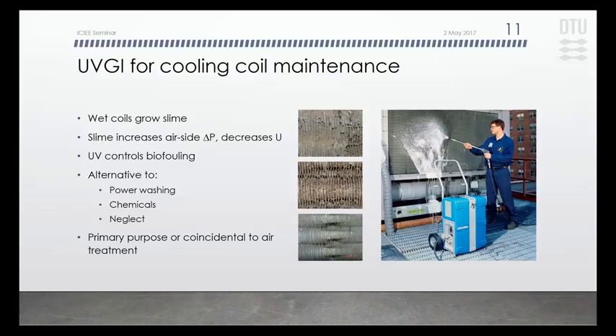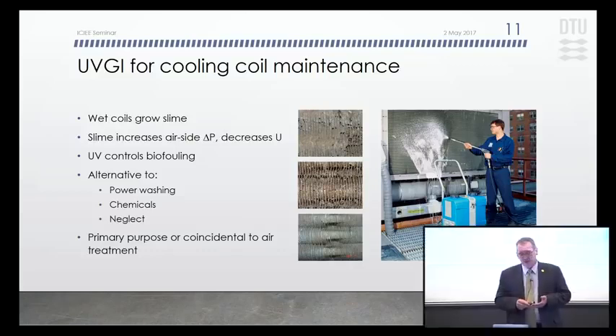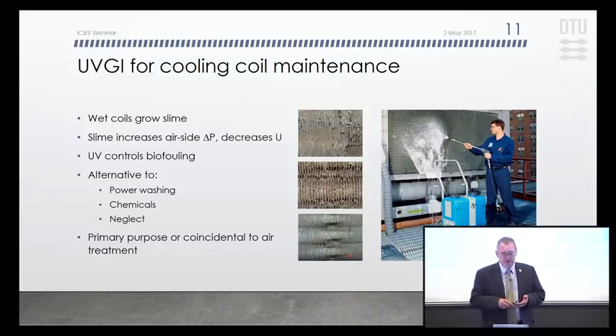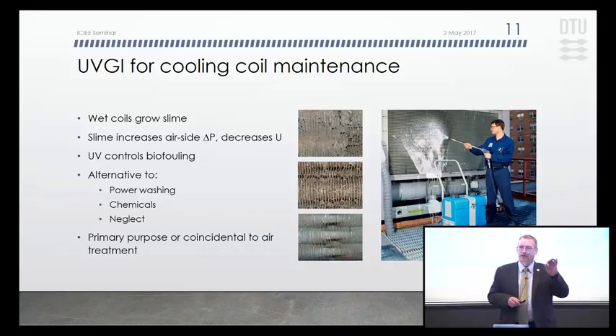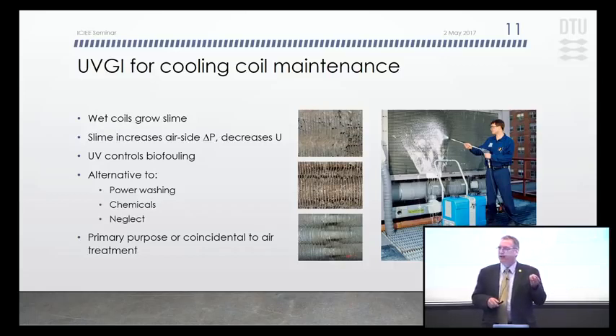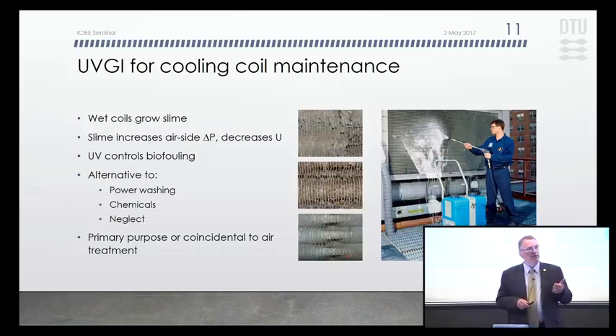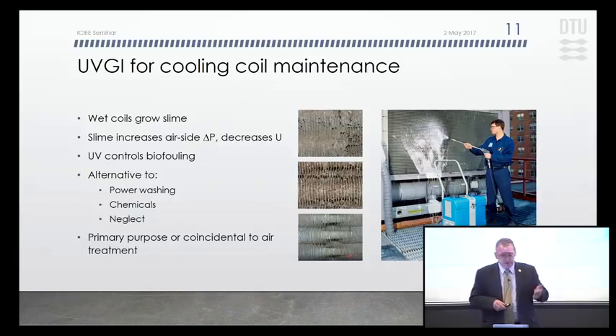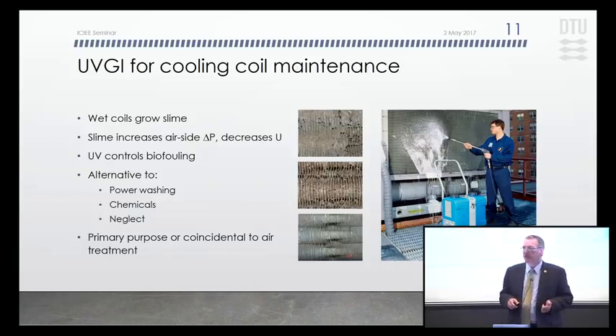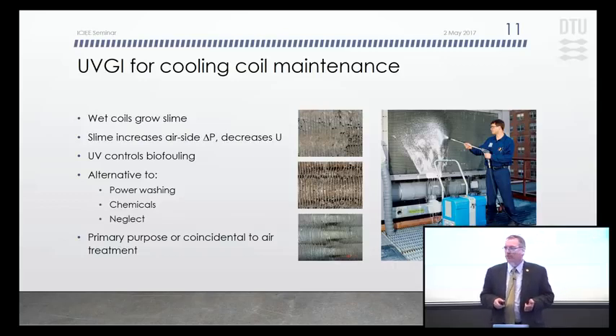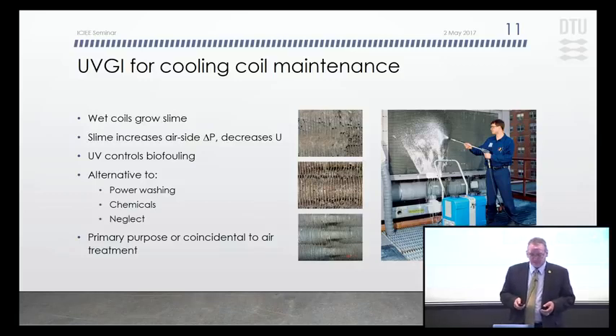So UVGI can do that, and it's an alternative to some not highly satisfactory alternatives like power washing, which often tends to simply push debris into the center of the coil, where it's more inaccessible and packs it together, rather than actually removing it. We can see someone doing that. Sometimes chemicals are used, which themselves create indoor environmental quality problems. And then the third approach to coil maintenance is neglect, which is also quite common. So many of them just become more and more fouled over time.